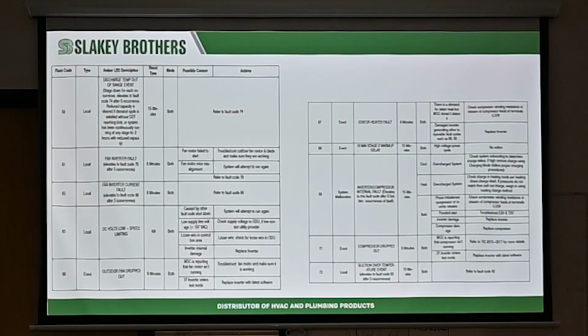The stuff where it gets, okay, crap, which one, what am I going to do now? What is it? When you really do get an inverter fault. But this is like a fan inverter fault. Fan inverter fault, that's what I'm talking about. Bam. It's going to tell you to go check out your voltage, or check out your inverter, your outdoor motor, because maybe the motor is just faulty itself. Simple. Just a little bit extra, kind of weird steps compared to a standard condenser fan motor, but it's going to be a simple check.